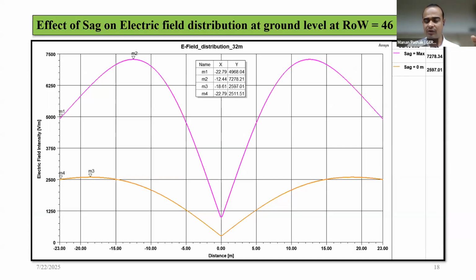As far as the hybrid transmission line is concerned, for a double circuit as per the Ministry of Power guideline, the 400 kV double circuit line requires 52 meters of right of way. But as per our result, which is authenticated and verified with the required publications, we secured the right of way within 46 meters just by changing the conductor positions and the movement of conductor placements, with and without considerations being incorporated.